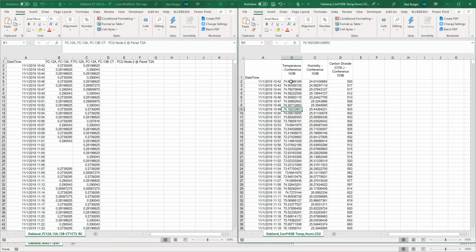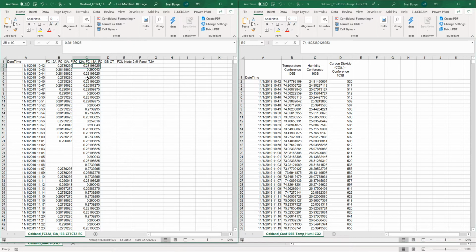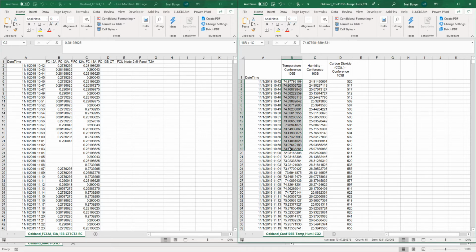Let's assume this fan coil power was 15-minute data. If I wanted to know the temperature, my recommendation at that point would be to average the 15 minutes of data we have here into one point and then use that to compare against the power reading we have here. And so all of that effort to normalize or to average data, to fix time, to combine them together, those steps will lose data quality.